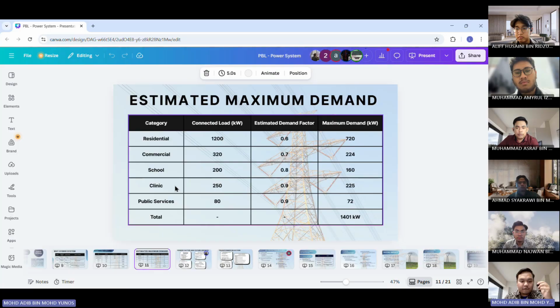720 kilowatt. But if we look at the clinic, I apply a much higher factor of 0.9, because in a medical facility, HVAC and diagnostic equipment run constantly. So we cannot gamble on diversity there. When we sum this adjusted load, residential, commercial, school, and clinic, our total maximum demand stands at 1,401 kilowatt. This is the baseline capacity we must guarantee today.